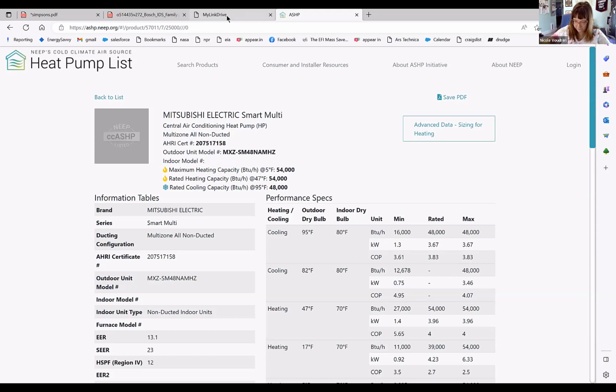Why is it that you are not worried about humidity? Yeah, because for Nicole's project, the cooling load is 25,000 BTUs per hour. And when I look at the min cooling capacity, I see that it's 12,000. So the min is a good chunk lower than the max, which tells me that this heat pump is going to be modulating through the vast majority of the spring and summertime.